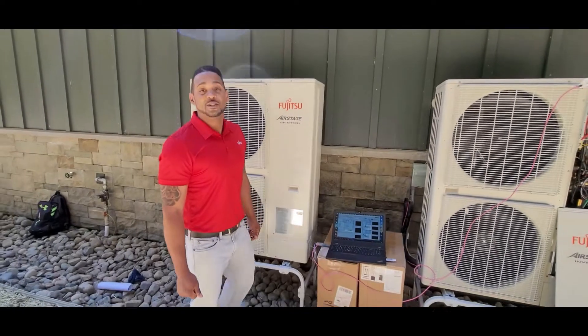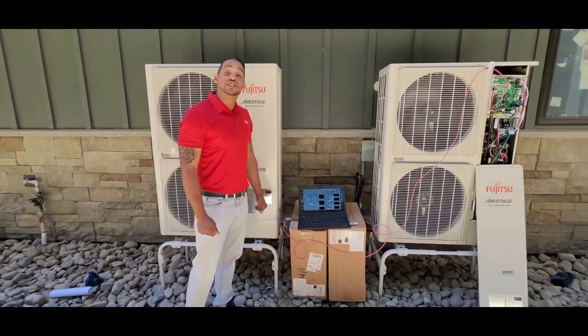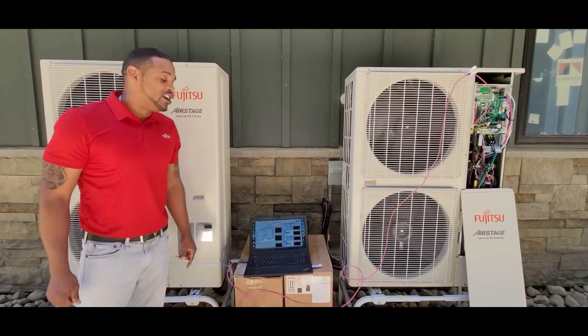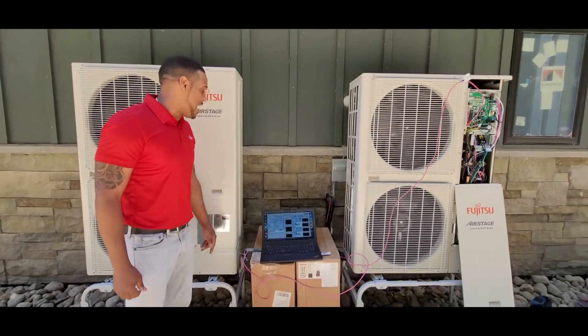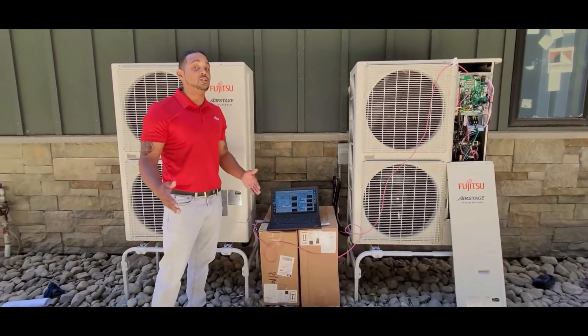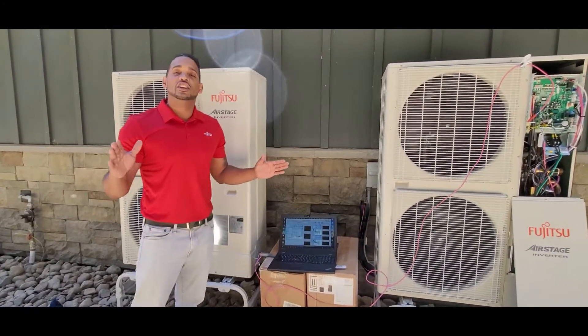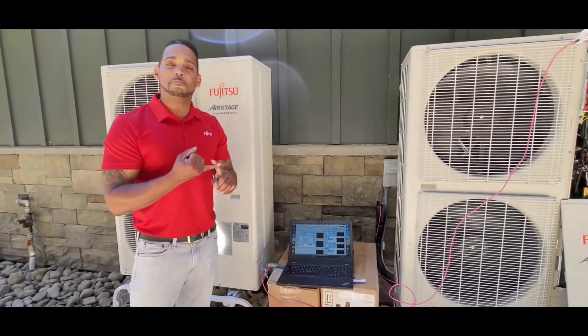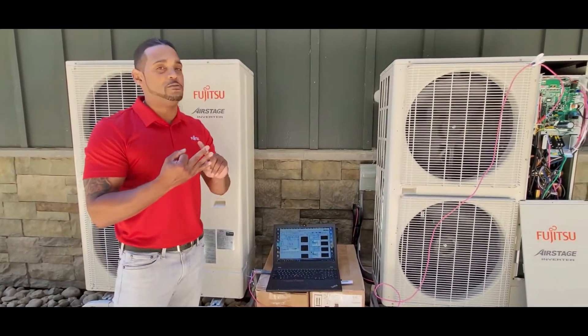Welcome back. As you see, we have two five-ton J-Series in operation — super quiet. Hooked up to our service tool that's on our laptop. You can see our operations of our units running indoor and outdoor, the complete refrigeration diagram, which shows you compressor fan operation, EEV pulses, and thermistor values.